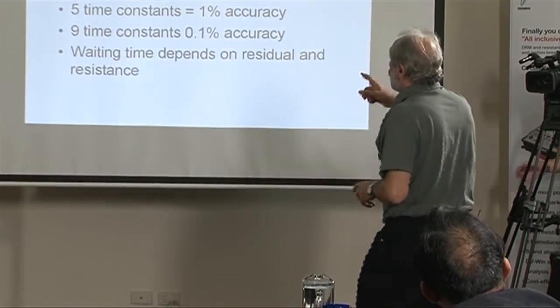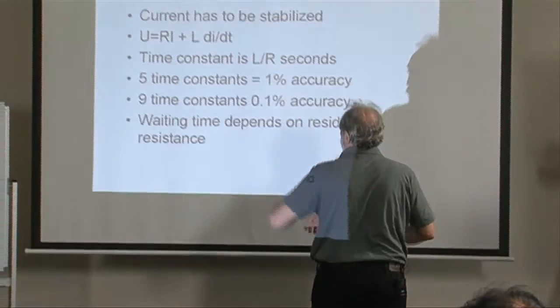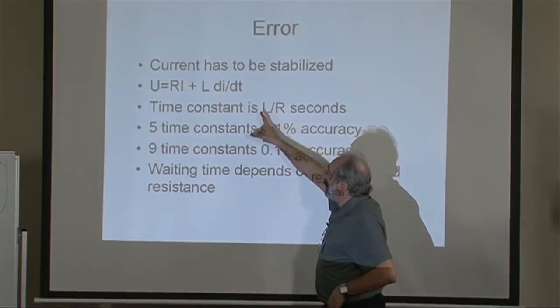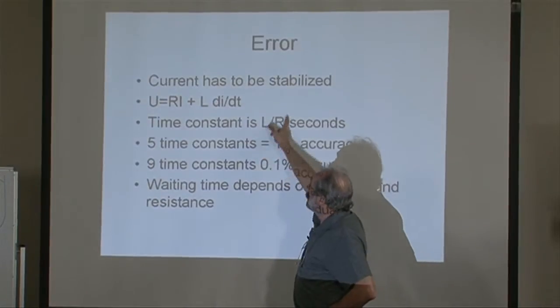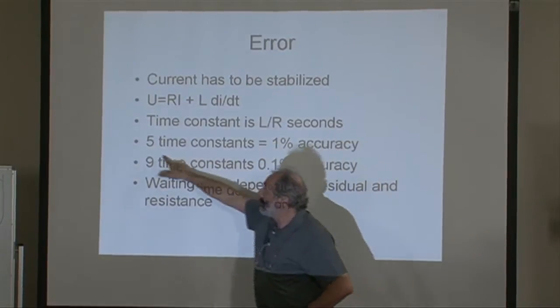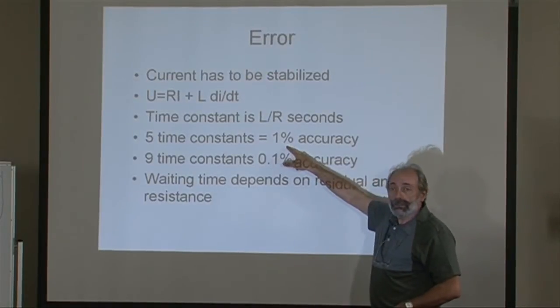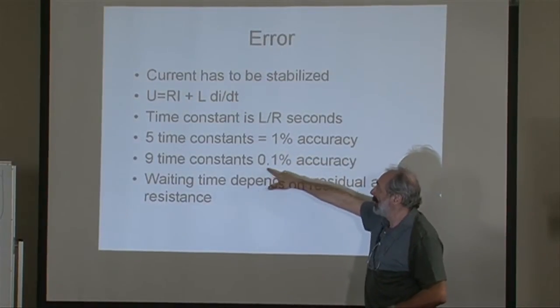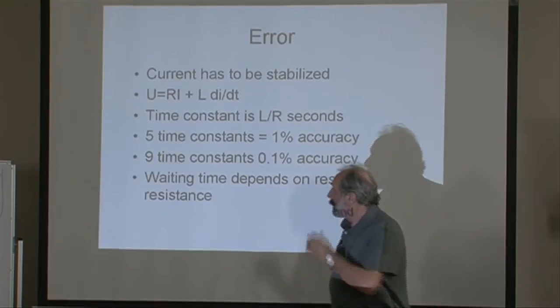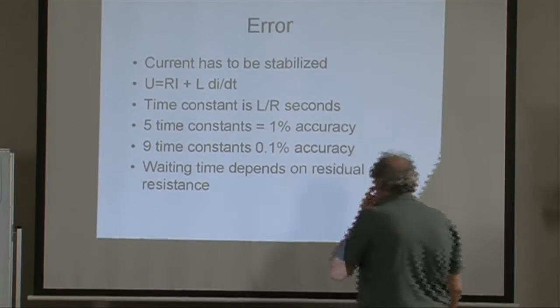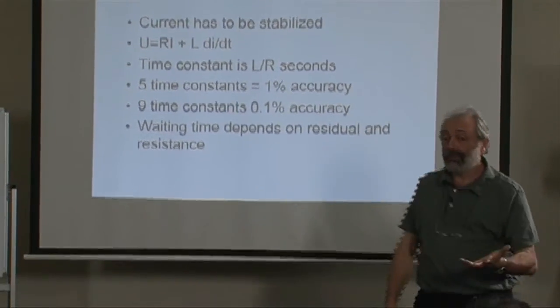Then you lower the inductance. I'll show you how you do that. But the important thing is, if this is my time constant: if I wait five time constants, I get one percent accuracy. If I wait nine time constants, it is 0.1 percent accuracy. And you know what?